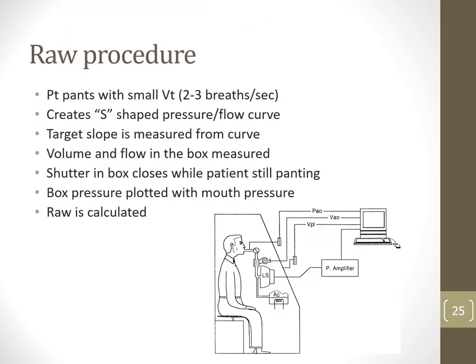So the patient will pant a couple of breaths, and this is going to create that S-shaped curve that you sort of saw on that previous graph. And that's going to look at the slope that we'll target on there. When they're doing this, like I said, that shutter in the box will close. And you do need to know which procedures require the shutter closing. I will ask you that. So please read the chapters.